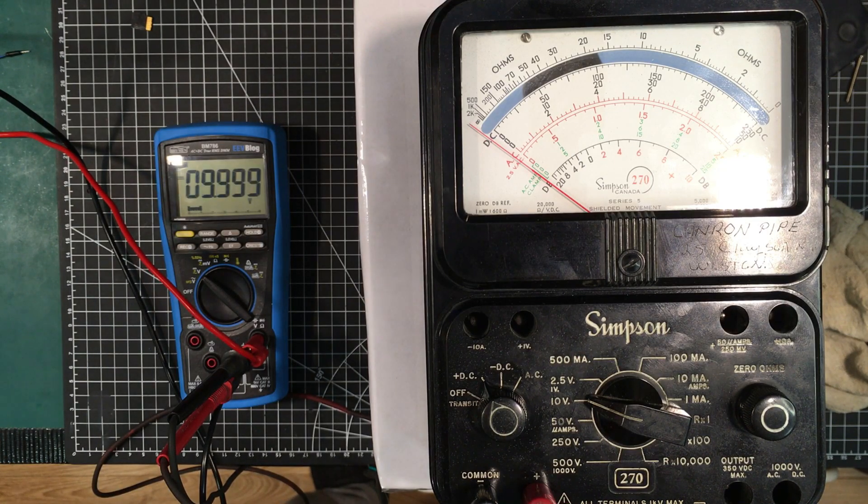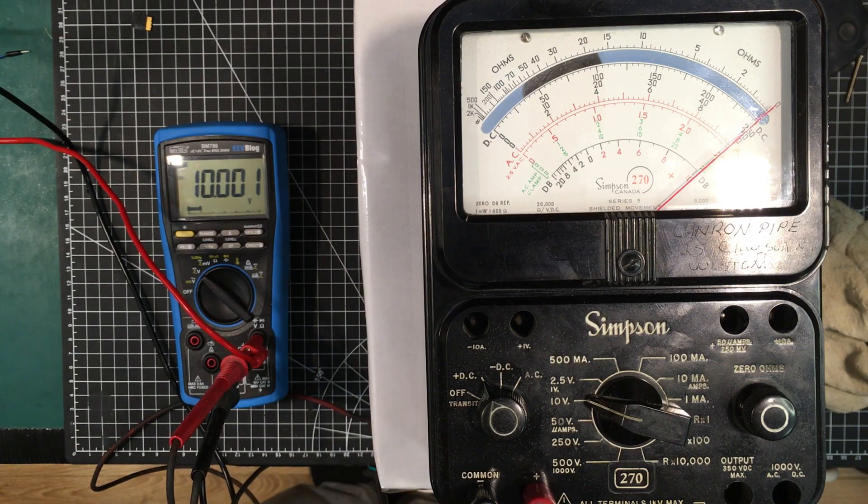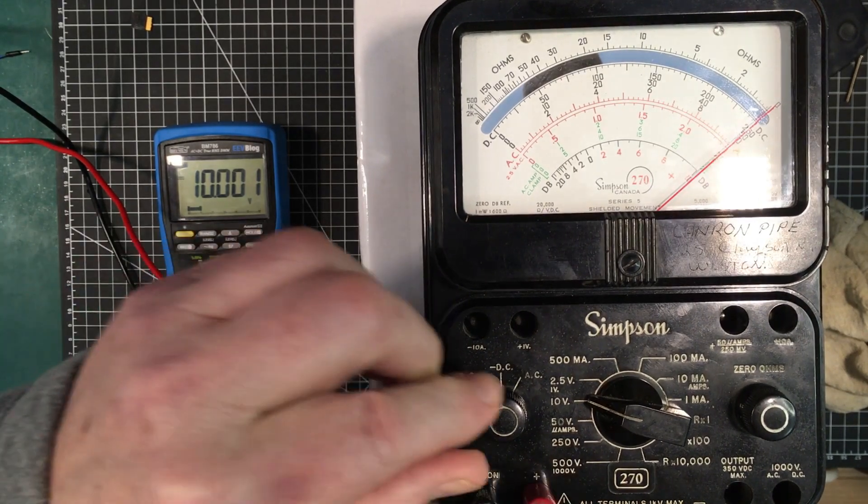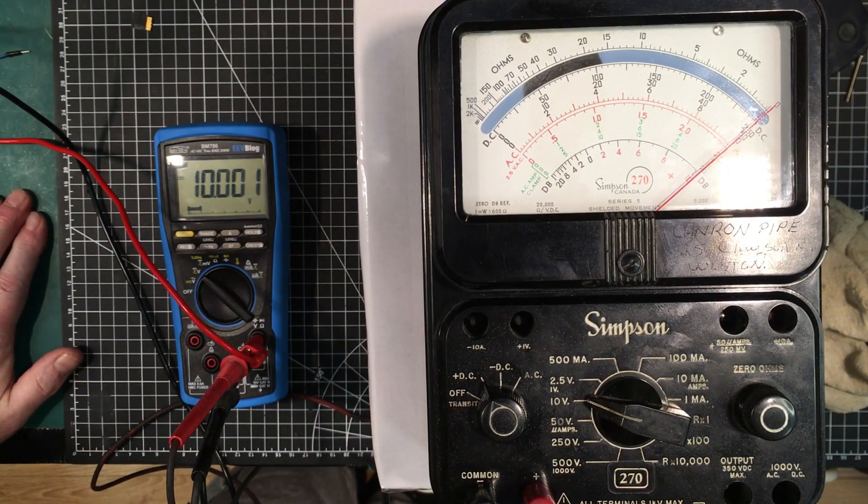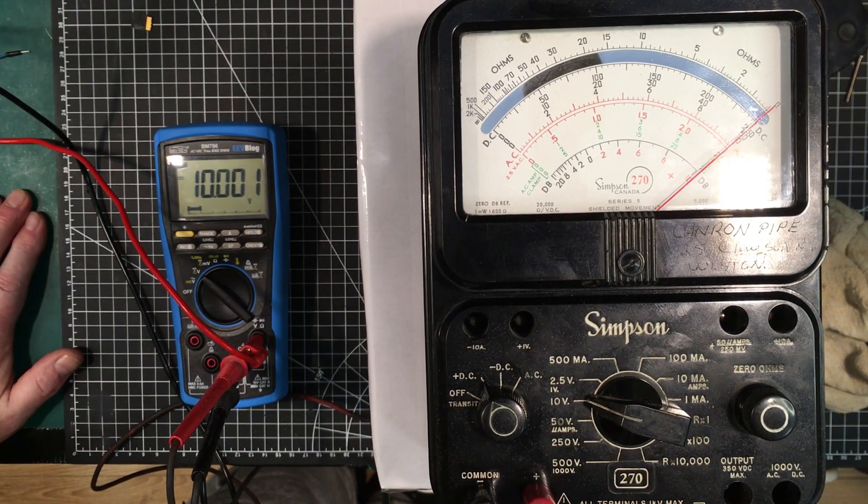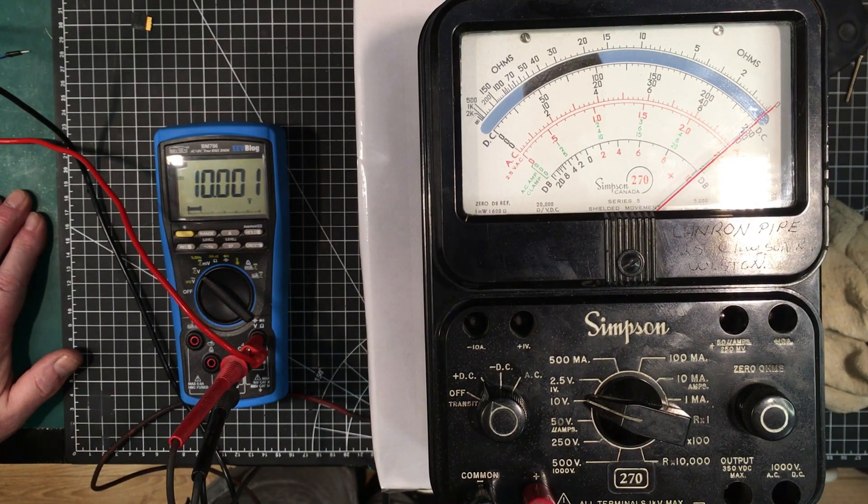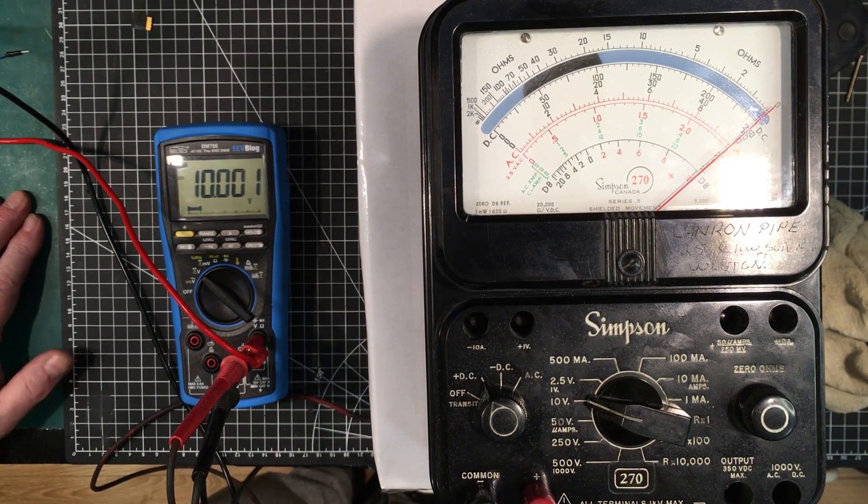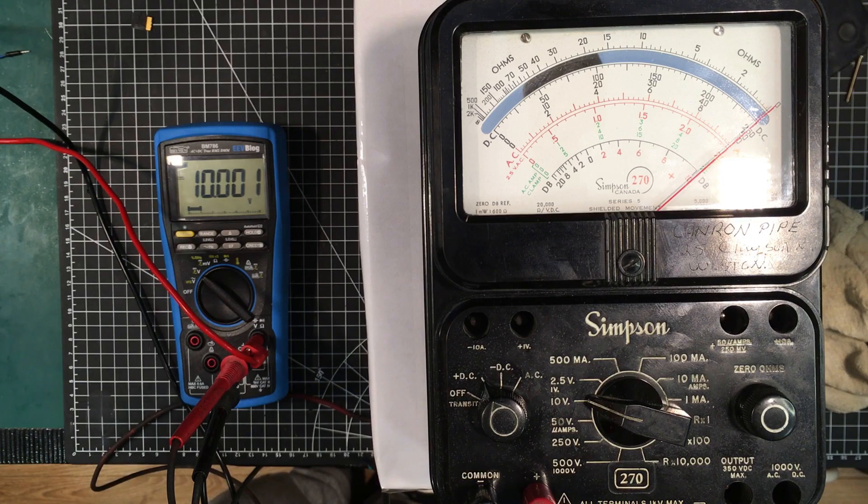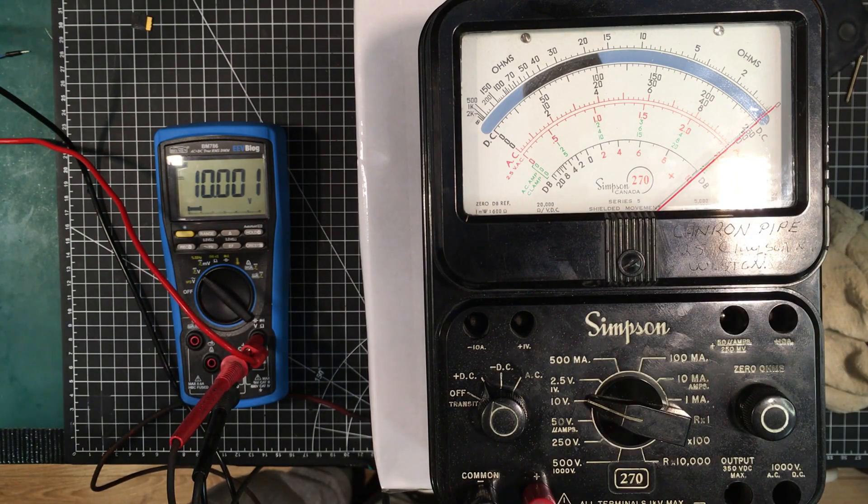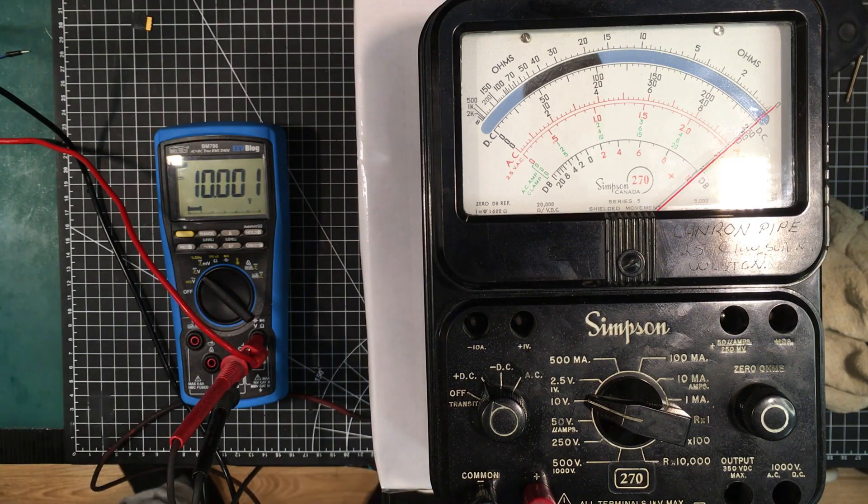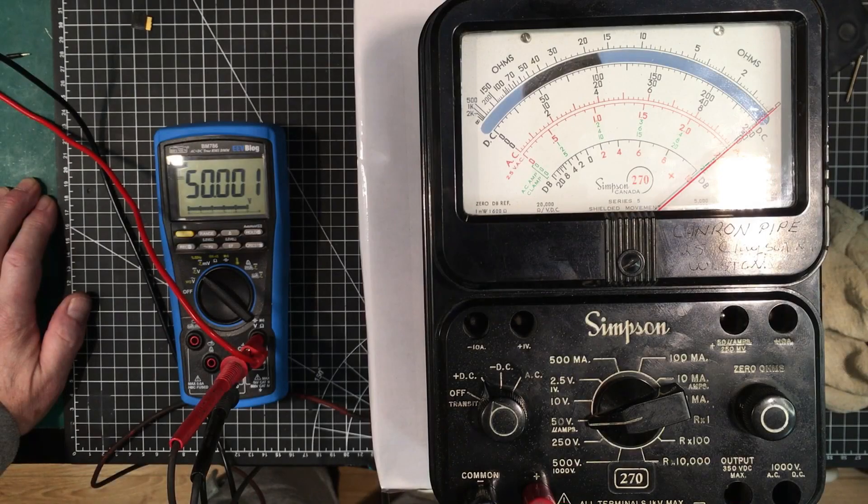I'm putting 10.0000 volts from my power supply. On the 10 volt scale I see that as being 9.9 volts. Is that within 1.75 percent? Yes it is, so that's within spec. It'd be nice to be able to trim that out but it's within spec and there's nothing we could do about it.